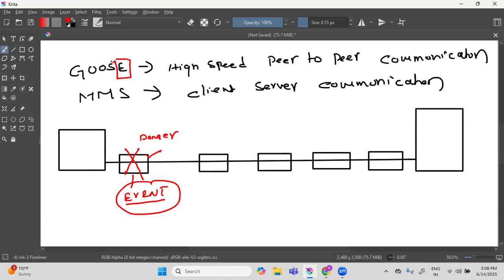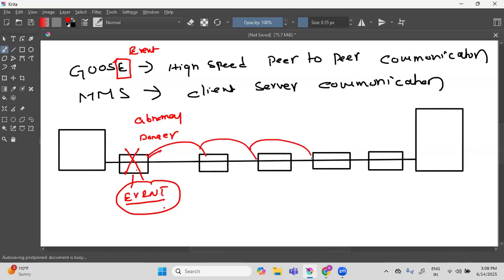What is goose? Generic object oriented substation event. Can you see this 'event'? This is event - meaning any abnormal activity happening. Now this relay has to immediately communicate to all the relays that there is an event, there is abnormal activity. All the relays should immediately switch off, off, off, off.